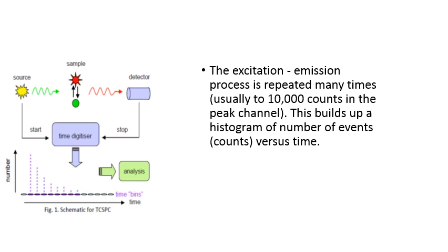So it is required to statistically count only one photon and it must not arrive during the dead time of timing electronics. In practical terms, the stop count rate needs to be limited to 2% of the excitation rate only. Failure to do so can lead to biasing towards detection of early photons.